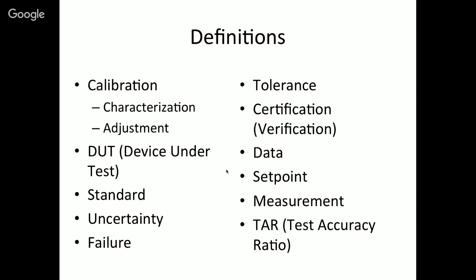Certification or verification is the characterization we mentioned before, but being done with some sort of legal backing to the actual instrumentation that the characterization is done with. Let's say that you're doing a calibration of a pH meter, and you've got standards that you've bought from Sigma Aldrich or Cole Parmer or wherever, and those have come with a certificate of calibration saying that they have verified those standards to be within such and such an uncertainty of like 7 pH and 9 pH and 3 pH or whatever your standards are at. Those are verified and certified.